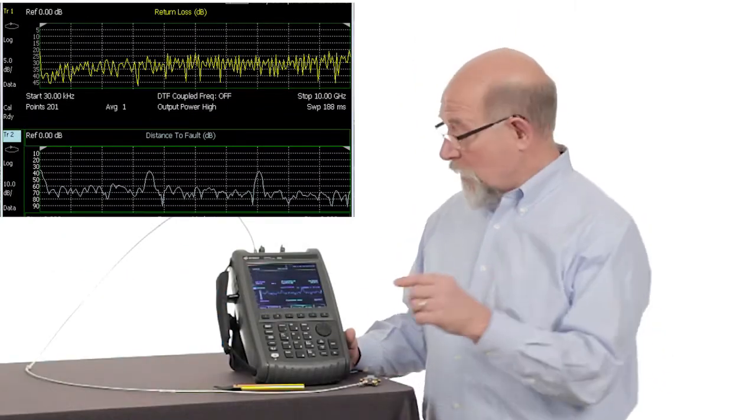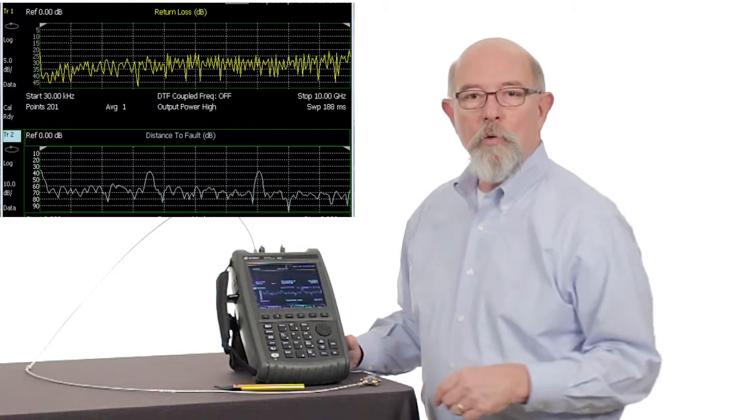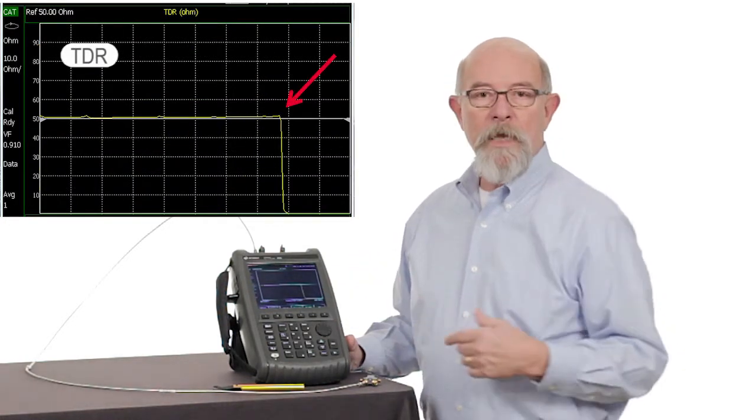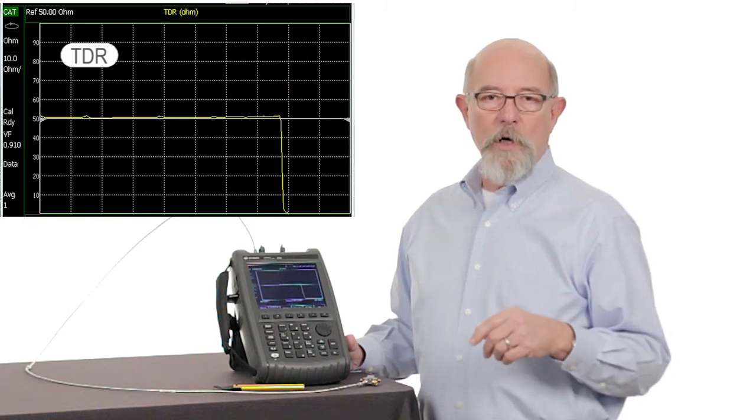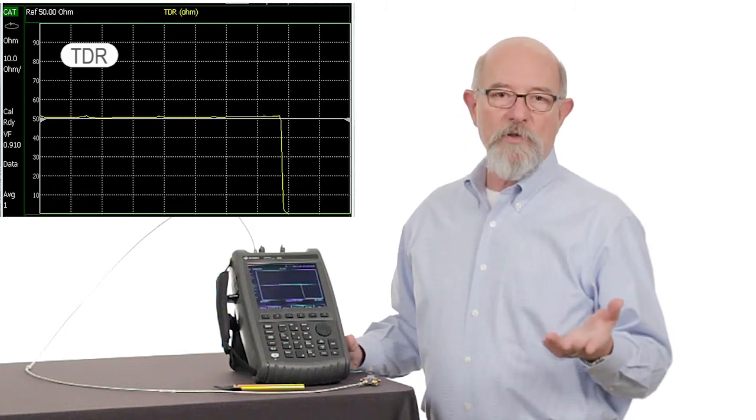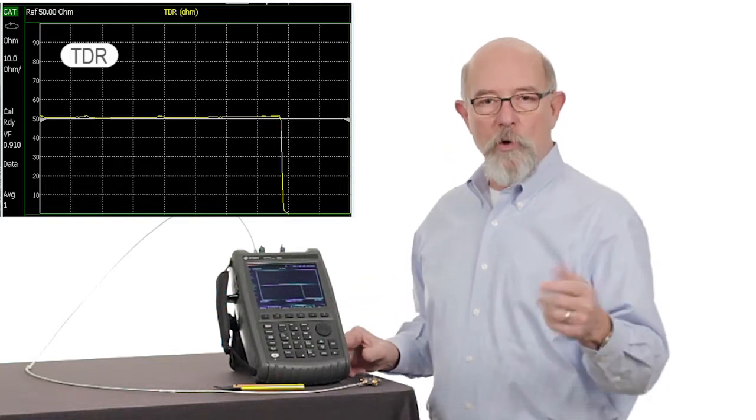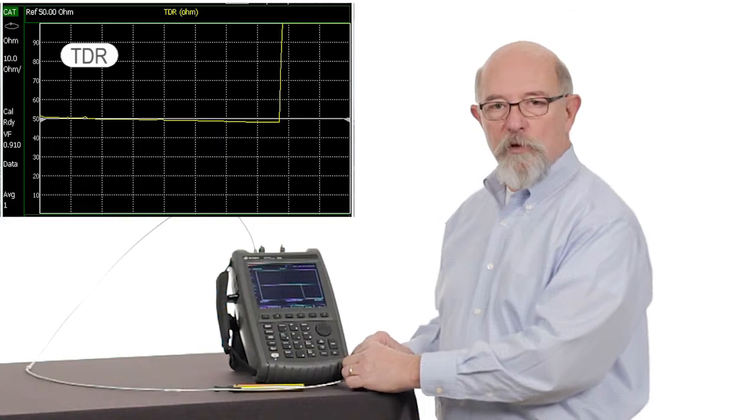By switching measurements to TDR, we can see that we have a good 50 ohm cable out to 2 meters. Then we see a short. After all, the short doesn't support voltage across its conductors, so by definition, it's 0 ohms. If we change the short to an open, the impedance moves to infinite.